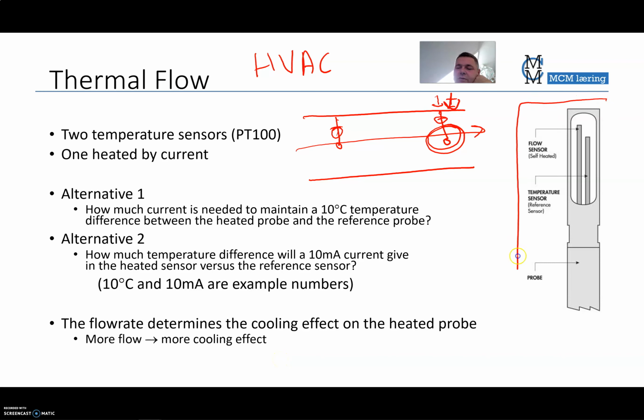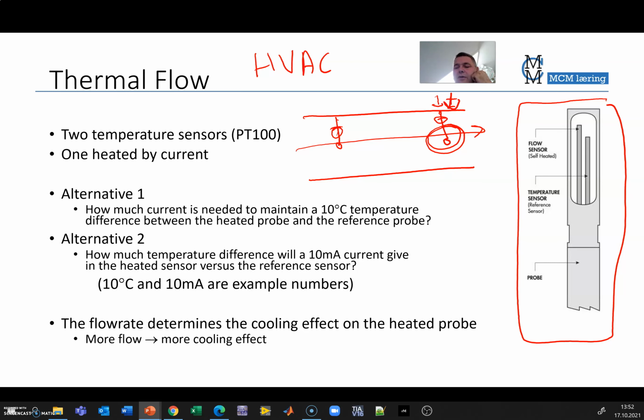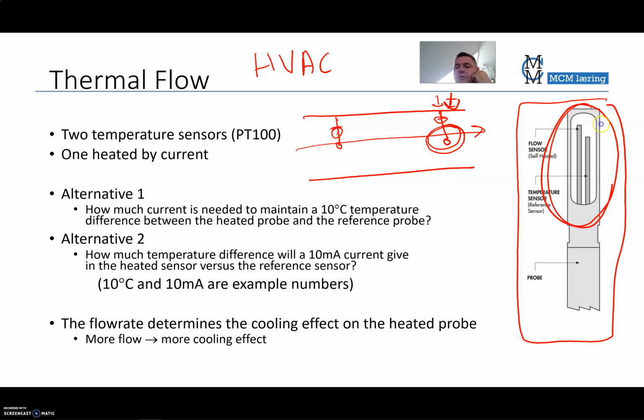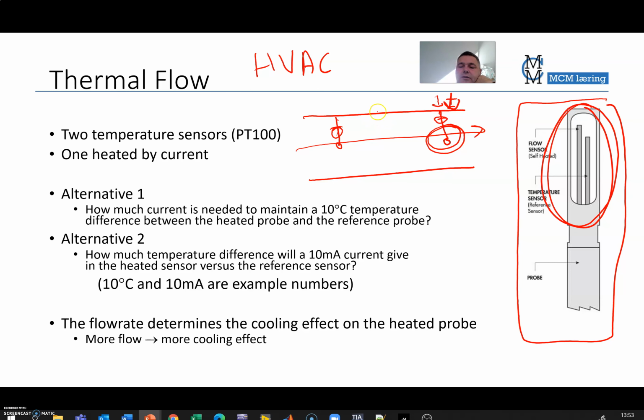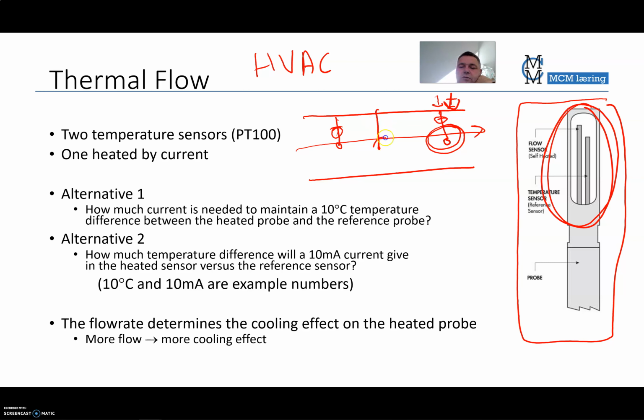As I said, it's very common in ventilation systems. You have to be careful where you place the sensor. Usually the sensor has two PT100s embedded in the same rod, and the rod should be installed so that the active area is in the middle of the flow.